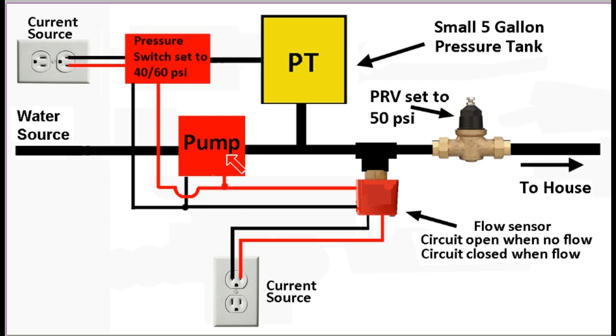Let's go to an initial state and go from there. Suppose the water is off. We have the pressure tank filled up to 60 pounds, as it should be. Now let's say you start using water. So what happens is you start using water, and water is coming out of this.